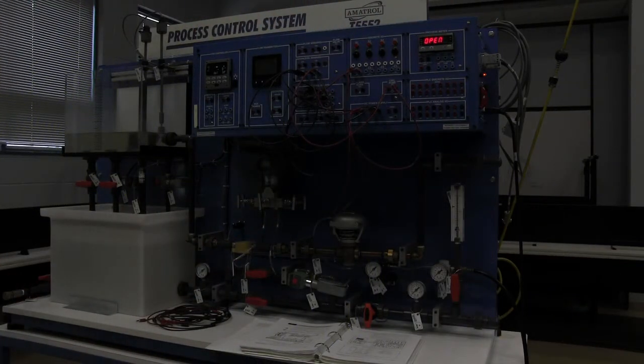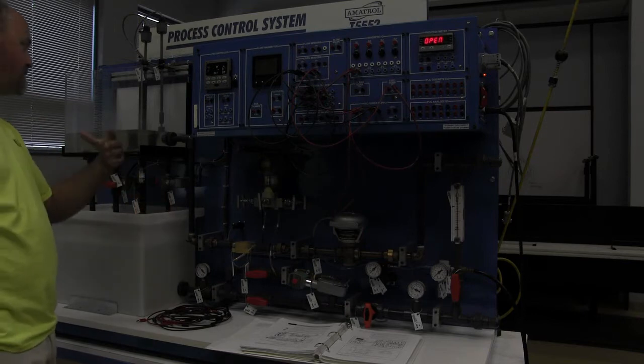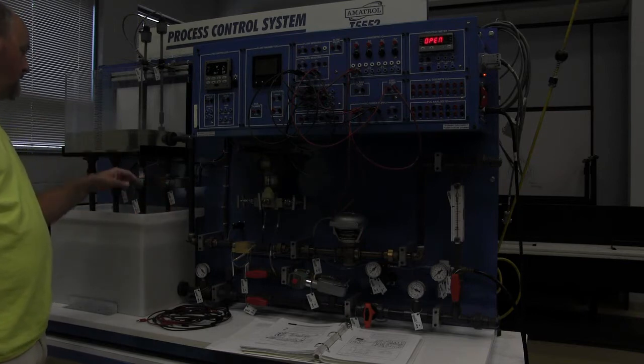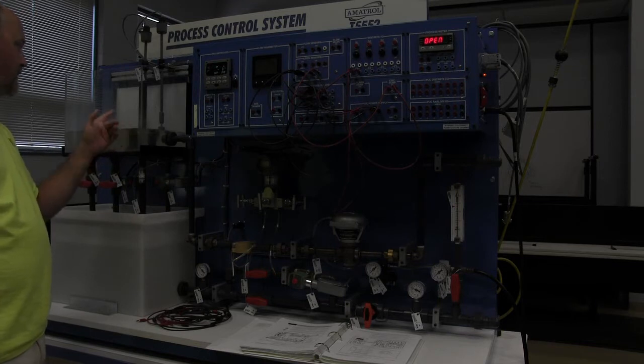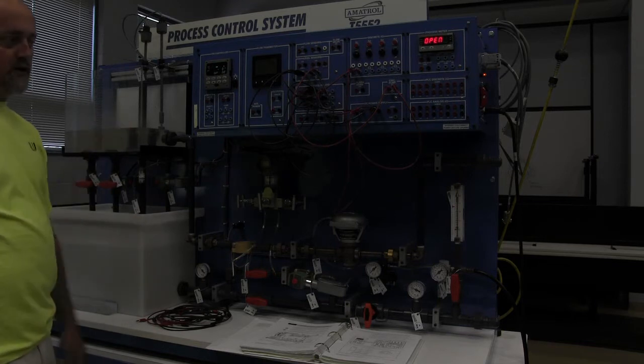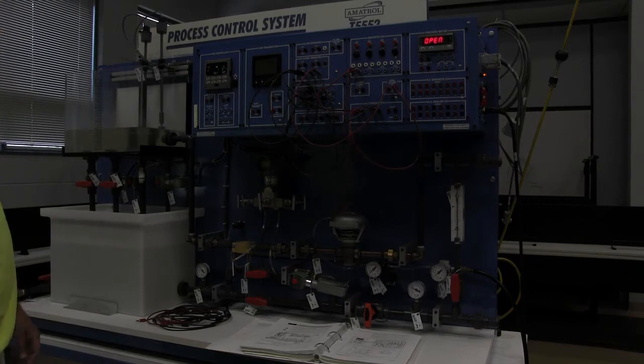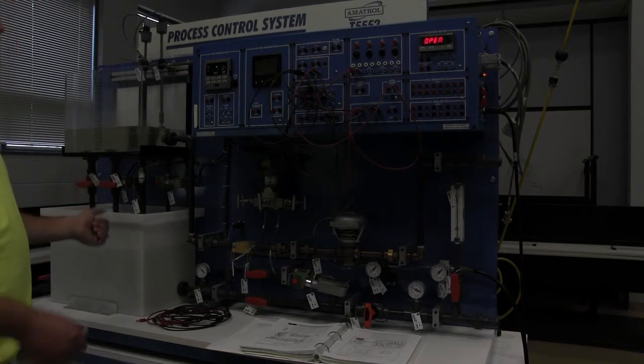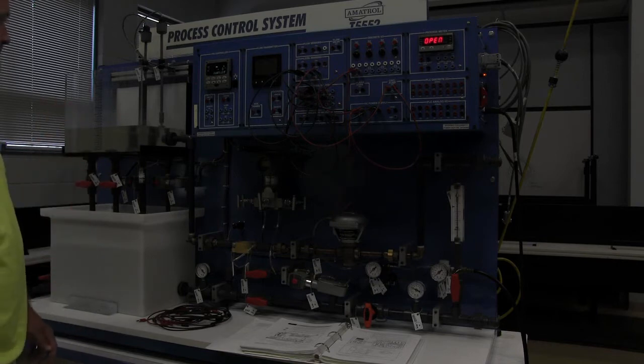We're getting really close to where that float has dropped. Once the float dropped, it said, okay, my level is low. The process pump has fired back up, the solenoid is closed, and the tank will start to fill again. Once it hits the high level float, it's going to do the exact same thing. So we'll watch that. Once we watch that, I'll drain it down faster. We'll see it come back on, shut it off, and we'll move on to the next lesson.